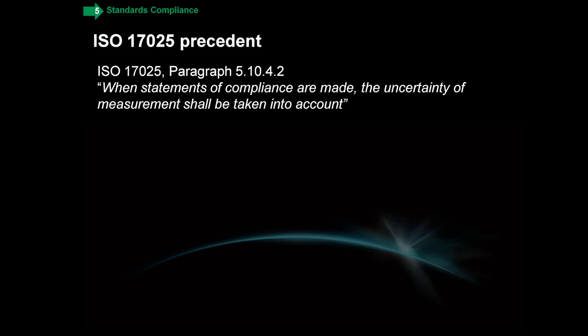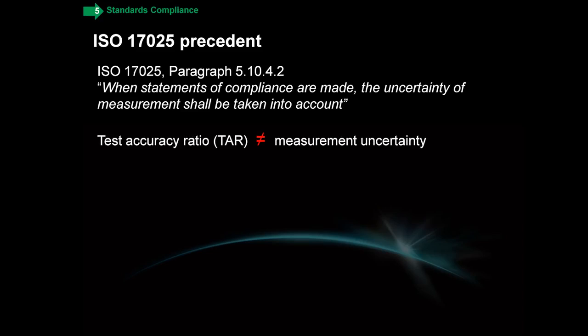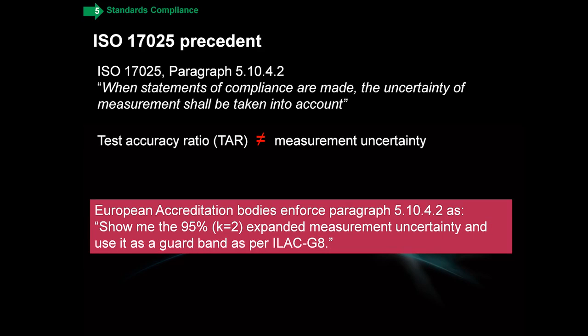There are all kinds of variations on this. Sometimes you hear, 'we did that — I've got our test accuracy ratio right here, we're all set.' Well, test accuracy ratio, as defined in the early 80s in MIL-STD 45662, is not the same as measurement uncertainty and should not be construed as such. For those of you in a European audience or in the Far East, many of your accreditation bodies enforce that paragraph as saying: use expanded measurement uncertainty as per ILAC G8, and guard band it.